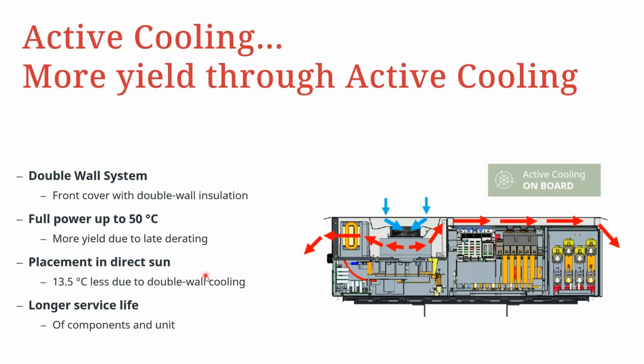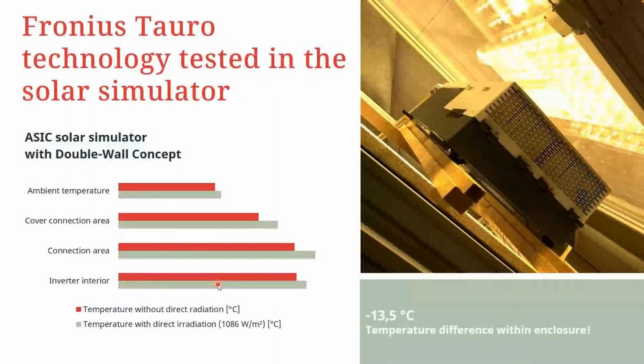With this double wall implementation, we're able to record 13.5 degrees less temperature than we would without it. We tested this technology using the ASIC solar simulator. With the double wall concept, looking at outputs in terms of ambient temperature, cover connection area, and inverter interior, we recorded 13.5 degrees lesser temperature.